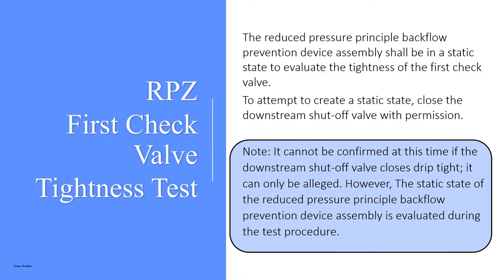The RPZ first check valve tightness test. The reduced pressure principle backflow prevention device assembly shall be in a static state to evaluate the tightness of the first check valve. To attempt to create a static state, close the downstream shutoff valve with permission. Note: it cannot be confirmed at this time if the downstream shutoff valve closes drip tight — it only can be alleged. However, the static state of the assembly is evaluated during the test procedure.